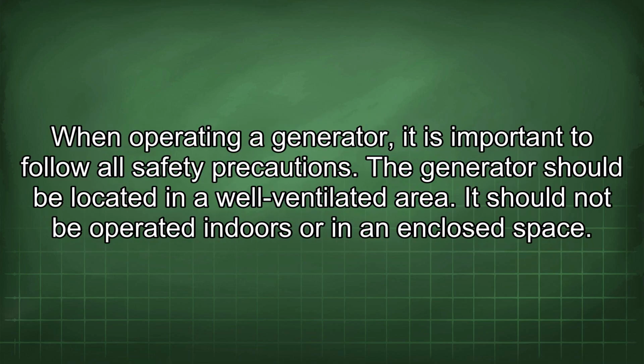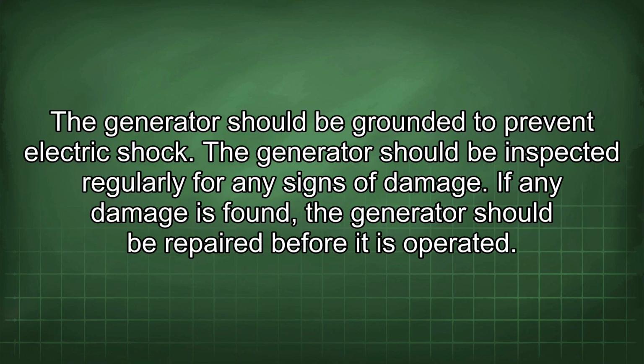When operating a generator, it is important to follow all safety precautions. The generator should be located in a well-ventilated area. It should not be operated indoors or in an enclosed space. The generator should be grounded to prevent electric shock. The generator should be inspected regularly for any signs of damage. If any damage is found, the generator should be repaired before it is operated.